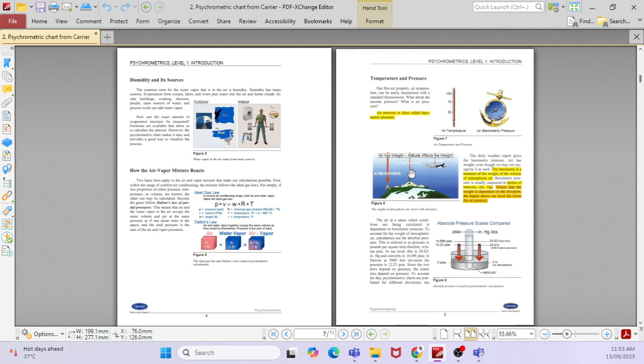Then the altitude. Remember, whenever we design air conditioning equipment and you request equipment selection, you also mention the sea level, the elevation. Why is it very important? What is the purpose of the elevation? Because as you go higher, your air density changes, right? That will affect your air conditioning equipment, whenever you try to cool the condenser, whether you supply dense air or less dense air, the machine load is increased. So you can understand that also. Try to create some quiz.